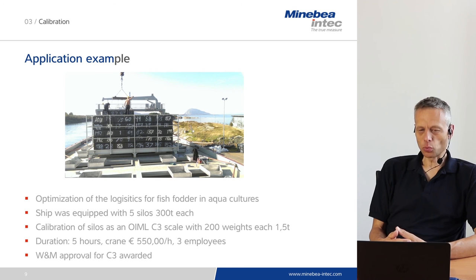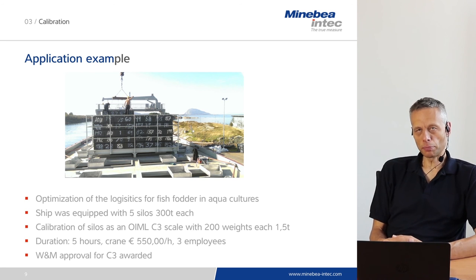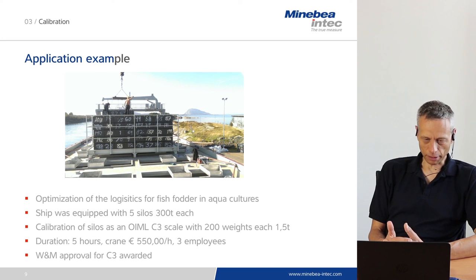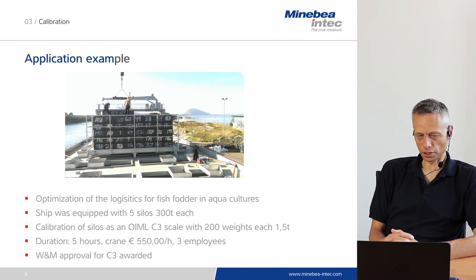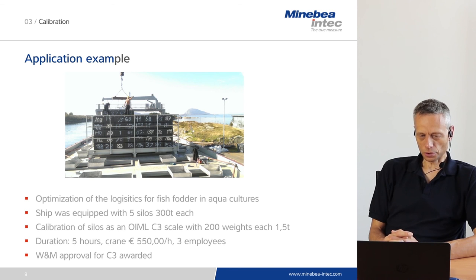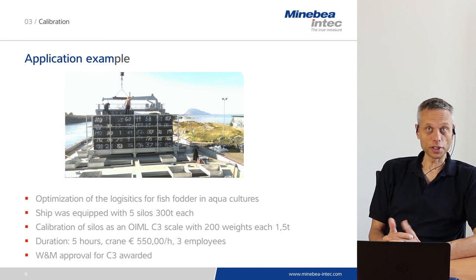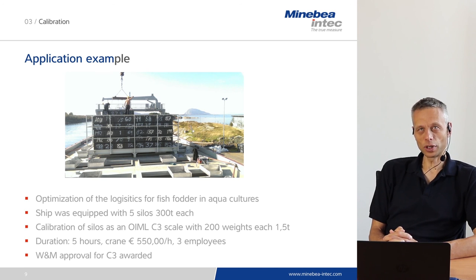This meant there was a requirement for a legal-for-trade scale with class C3 load cells, making calibration with weights absolutely mandatory. Two hundred weights with a capacity of 1.5 tons each were loaded step by step onto each silo using a crane and manpower. The duration per silo calibration was five hours. A crane was used at a cost of 550 euro per hour, plus three employees. Finally, the accuracy of the system was so good that the weights and measures approval for a class C3 scale was awarded, showing that this accuracy can be achieved — but the amount of work and material required is quite high.